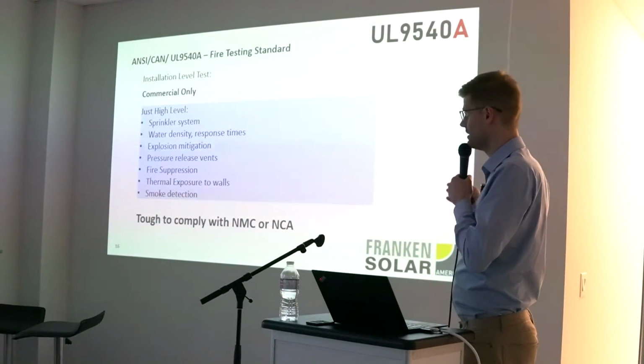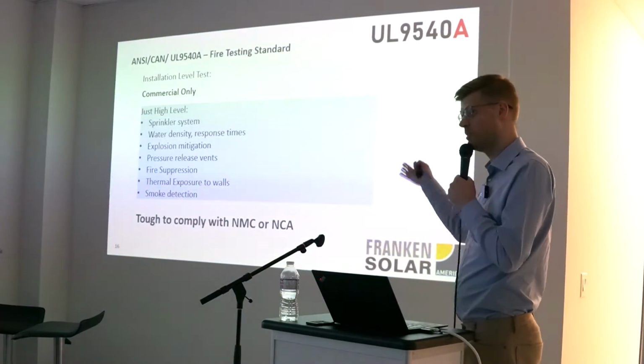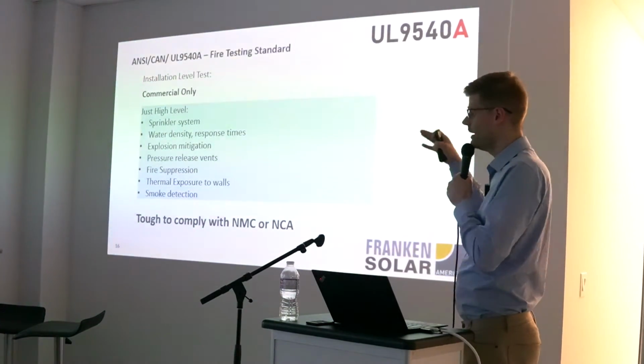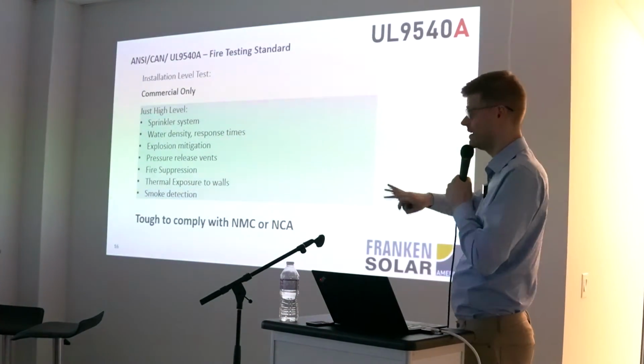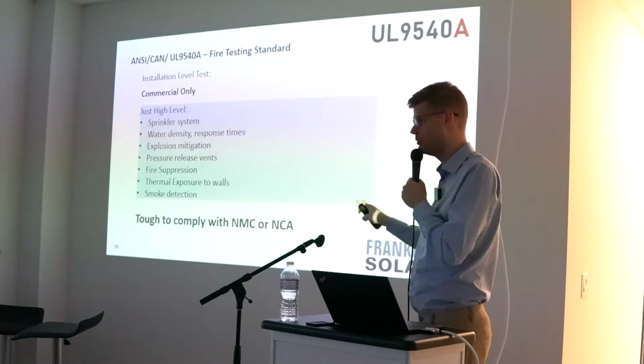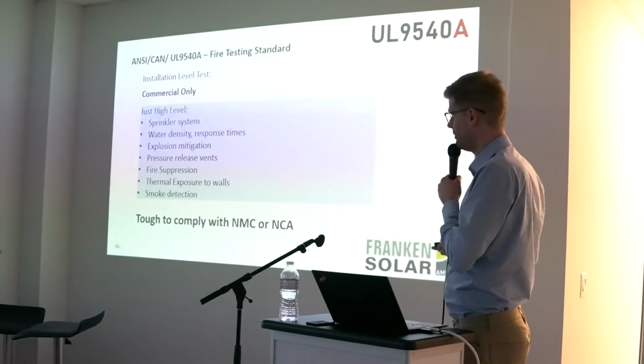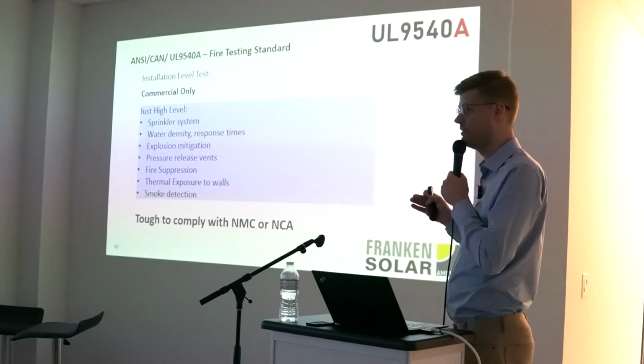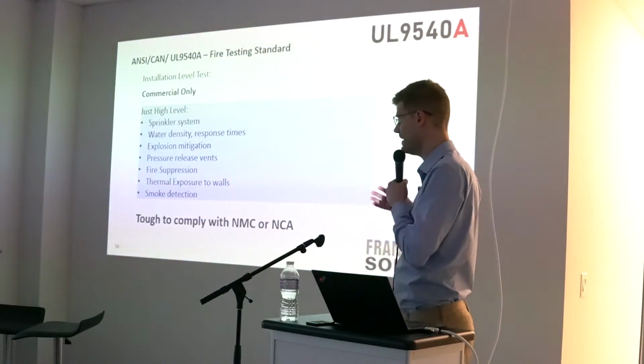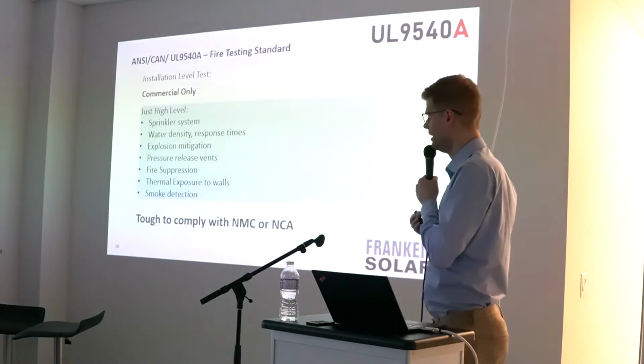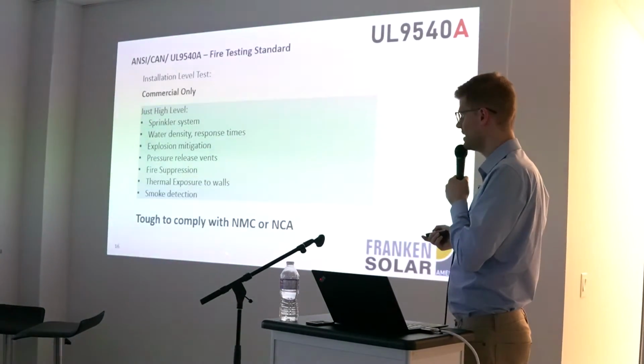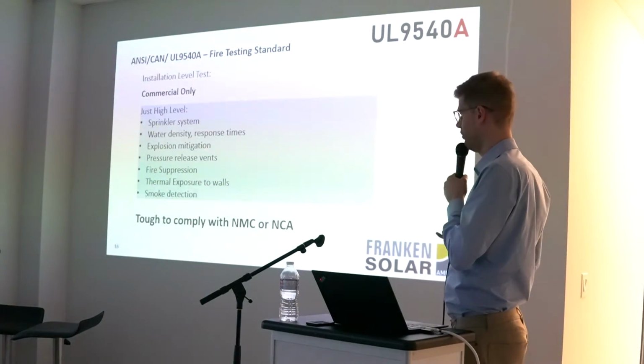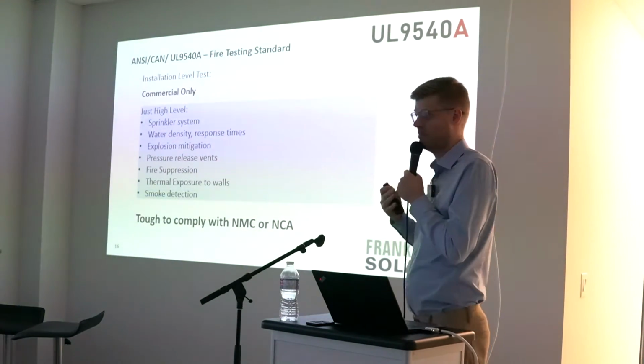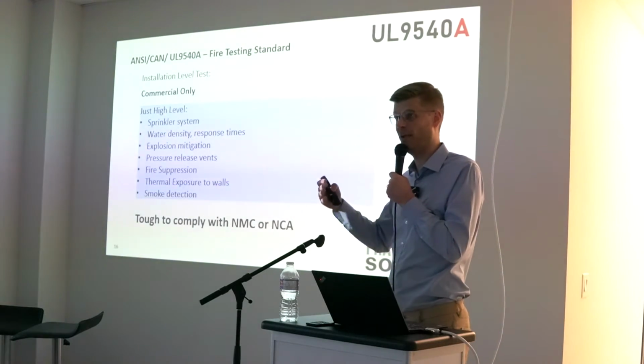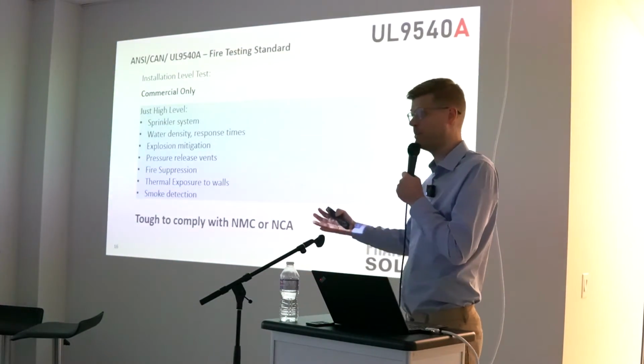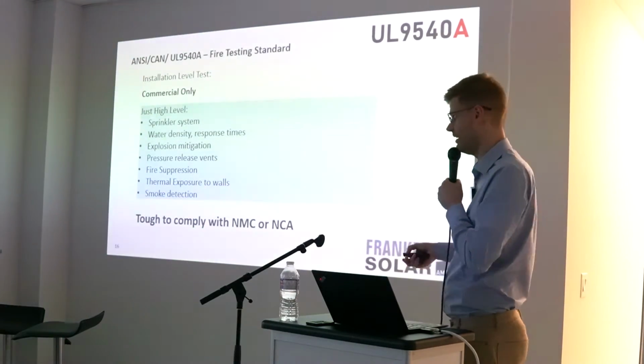Thermal exposure to walls, things like that. Smoke detection needs to be connected to an alarm system. And they can pick and choose whatever they need to pass that inspection. Again, that's very high level for commercial. We don't want to go too deep into it. But what I'm writing here is that it's very, very tough to comply with the 9540A fire testing or large fire testing if you use an NMC cell, like typically used in automotive, or an NCA cell, which has a much, much higher likelihood of a thermal runaway, and then the amount of heat being produced and dissipated is significantly higher than LFP.